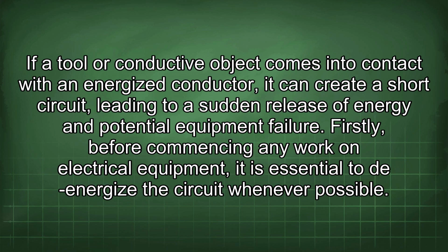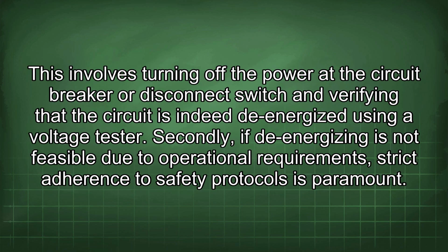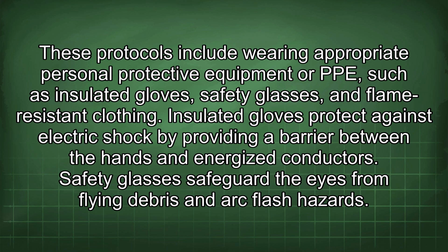Firstly, before commencing any work on electrical equipment, it is essential to de-energize the circuit whenever possible. This involves turning off the power at the circuit breaker or disconnect switch and verifying that the circuit is indeed de-energized using a voltage tester. Secondly, if de-energizing is not feasible due to operational requirements, strict adherence to safety protocols is paramount. These protocols include wearing appropriate personal protective equipment, or PPE, such as insulated gloves, safety glasses, and flame-resistant clothing.